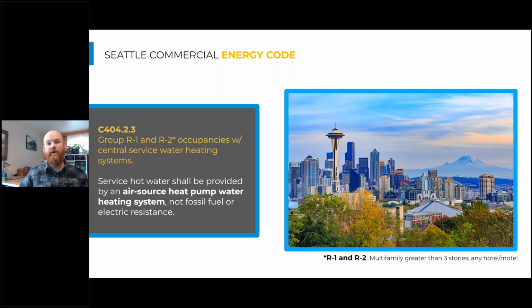The Seattle Commercial Energy Code is now requiring heat pump water heating systems for multifamily and hotel motel. That's R1 and R2 occupancies. This is a requirement as of this year, 2022, so we're 3 months in right now. But essentially, service hot water shall be provided by an air source heat pump water heating system, not fossil fuel or electric resistance. There are other exceptions in there for water source heat pump water heaters in certain building types and systems. But in general, we're talking about multifamily buildings and hotel motel here that it is now required to do.